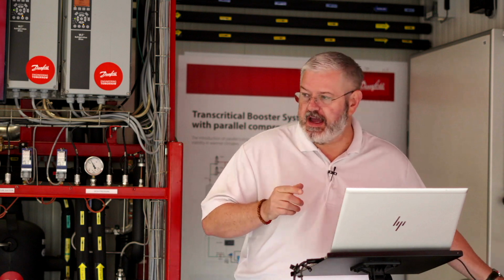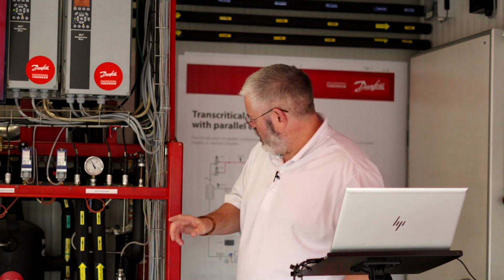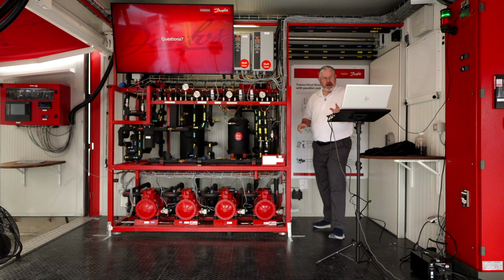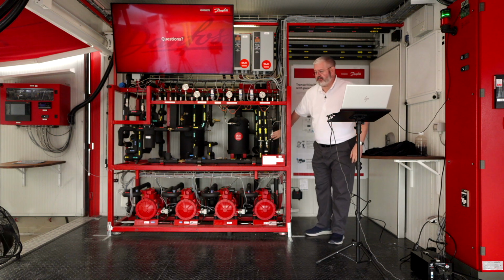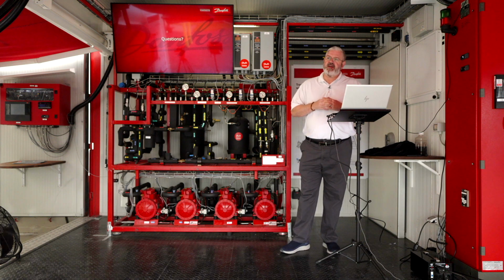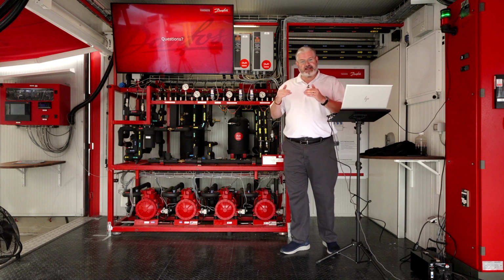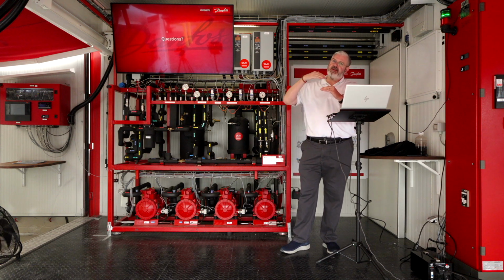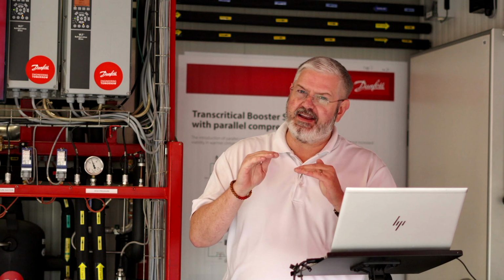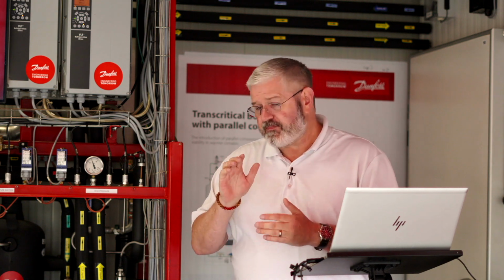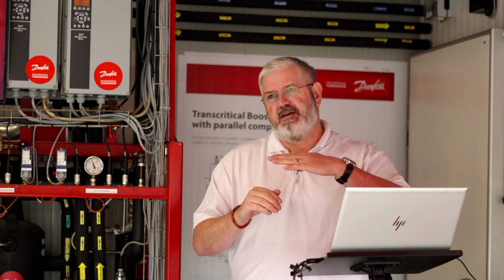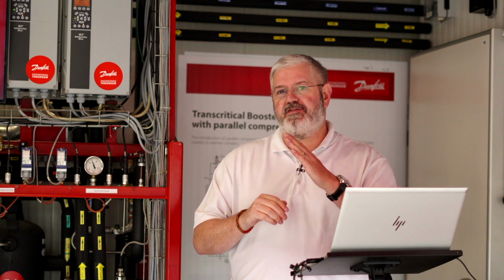What determines when parallel compression is turned on and off? So what happens with the parallel compression? We've got a valve here, which is our receiver valve. We tell it in the software, if you look for the settings for parallel compression, there's not really an area. It's in the receiver valve settings. And you basically tell it, start the IT compressors. We call these IT for intermediate temp. There's low temp, medium temp, and then intermediate temp, which sounds better than high temp, I guess, is why they chose intermediate.